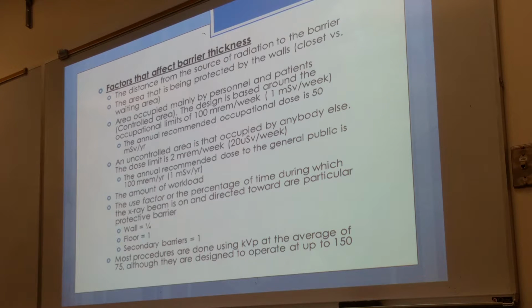An uncontrolled area is one that is occupied by anybody else other than personnel and patients. The dose limit is 2 millirems per week. The annual recommended dose to the general public is 100 millirems per year. It's also going to depend on the amount of workload in that particular room.